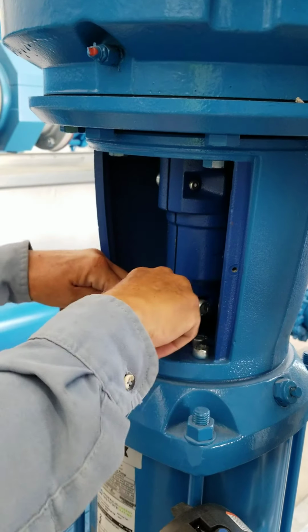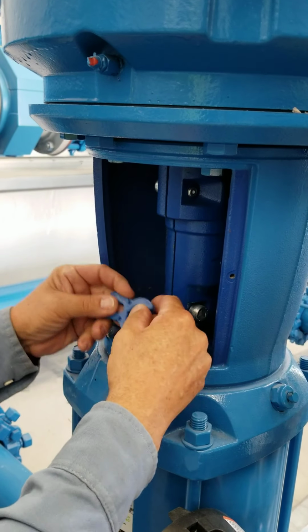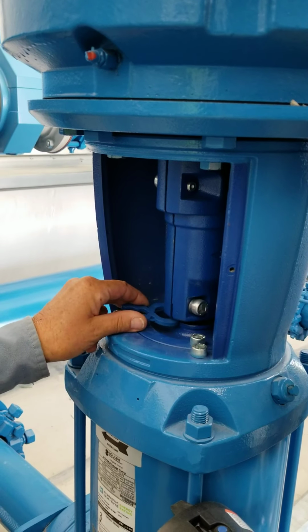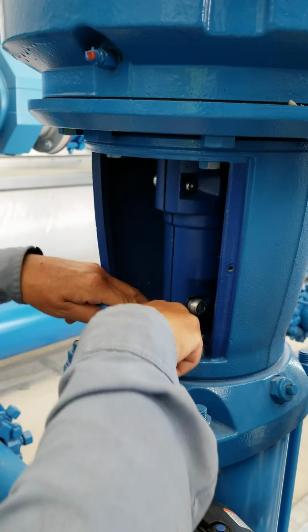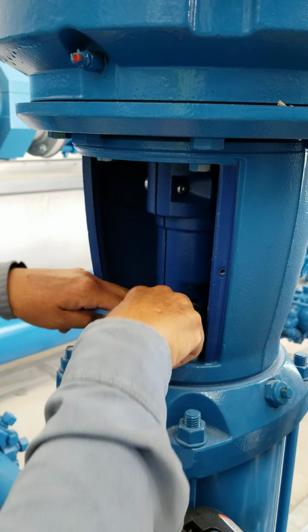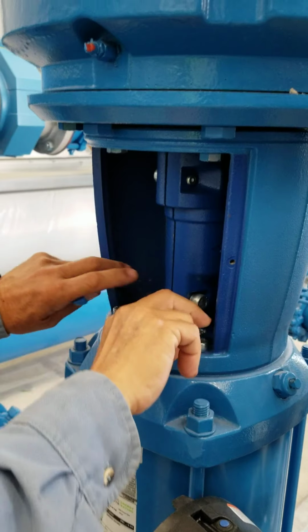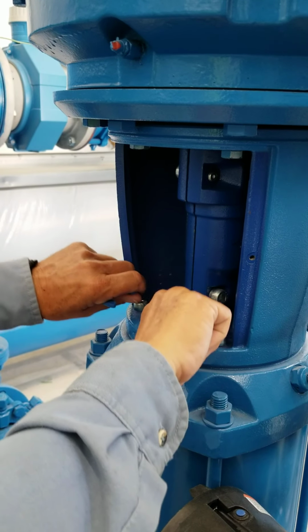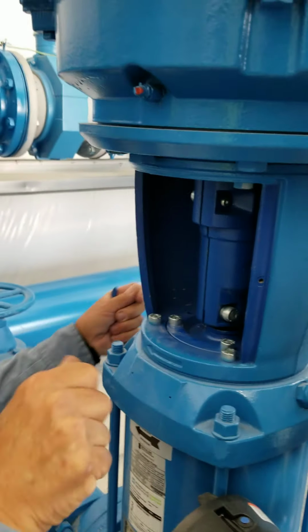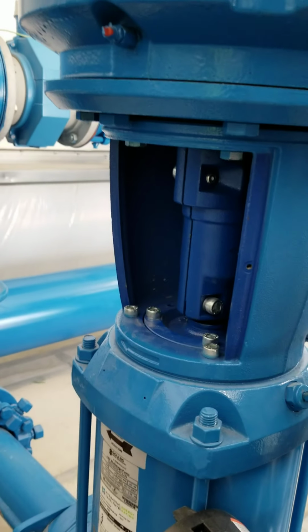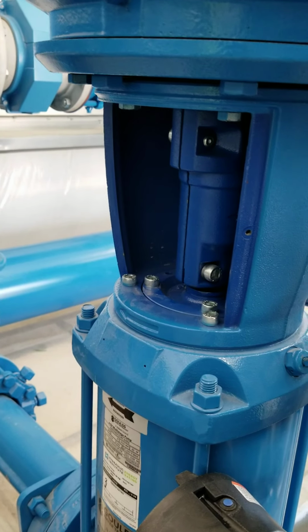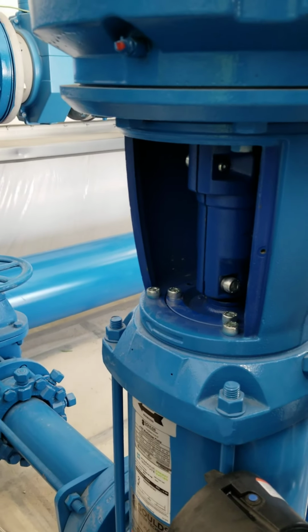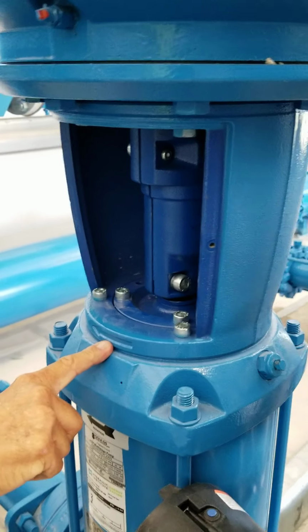This is your four screws holding your housing down. That's your gap that you want to set your seal at. So when you take these four bolts off, you're going to take this plate off, and then the seal is right there. If it's a little tight, I use two little screwdrivers. Pull it straight up. They're so user friendly. I love this style of pumps too. And then show them the rotation. The rotation marks are right there.